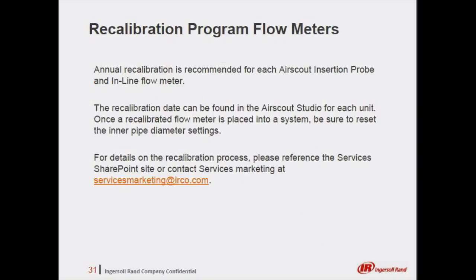Recalibration of all Airscout flow meters is recommended on an annual basis. Ingersoll Rand has developed a recalibration program with stock of recalibrated flow meters at the DLC as part of an exchange program. The recalibration date can be found on the Airscout Studio for each unit. Once a recalibrated flow meter is placed into a system, be sure to reset the inner pipe diameter settings. Additional details on the flow meter recalibration process are available on the Services SharePoint site or contact Services Marketing at the email listed on the slide.